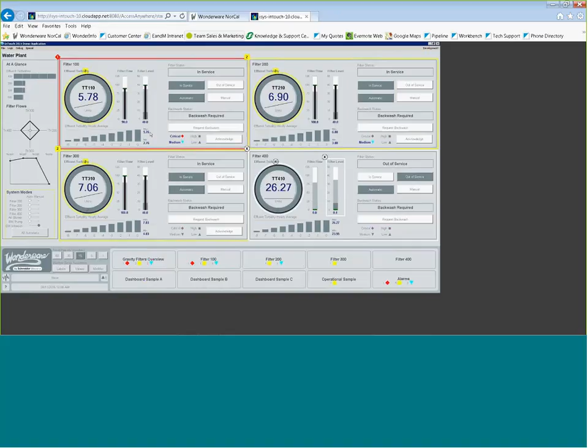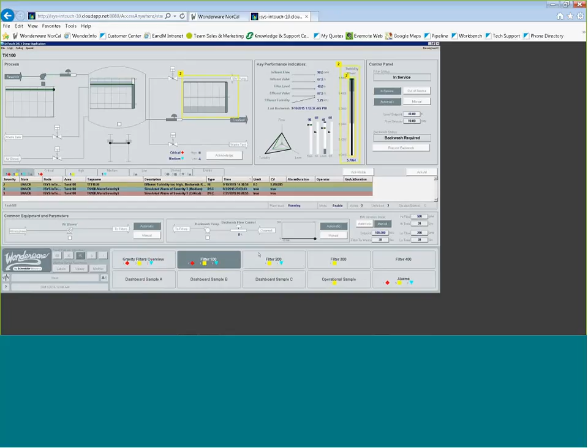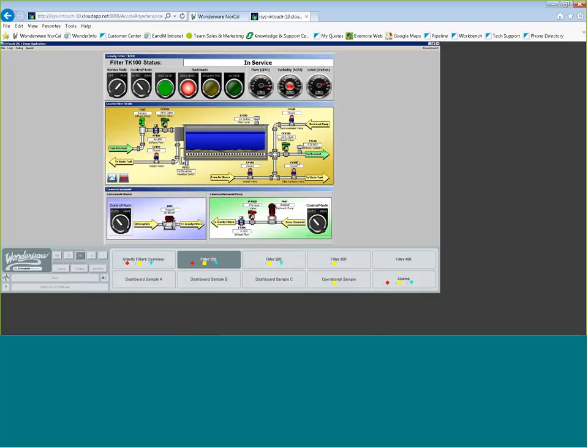Now I've got my situational awareness dashboard here. I'm looking at my different filters, and I can drill down into a specific filter to see what's going on. I can see I've got some alarm borders here, some high levels. I can see my situational awareness trend pens here, so I can see what I've been doing over time, whether I'm staying within my target region. I can see I've got a turbidity event here—those are alarm borders. Then if I want to operate my plant, I can drill into the operational HMI and see my traditional HMI screen to operate the plant.